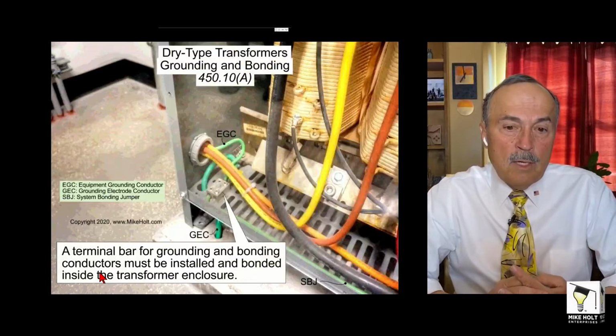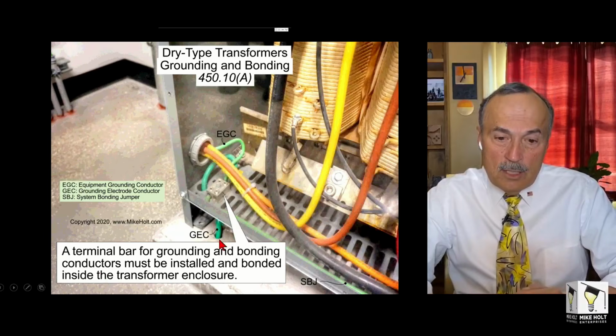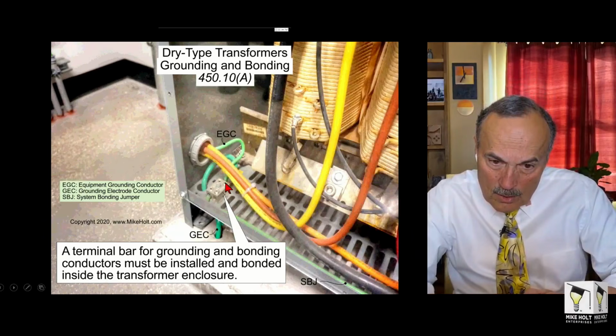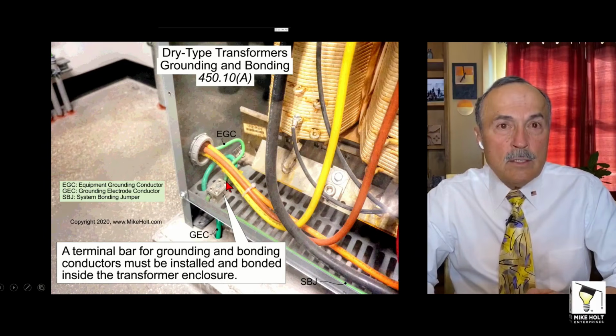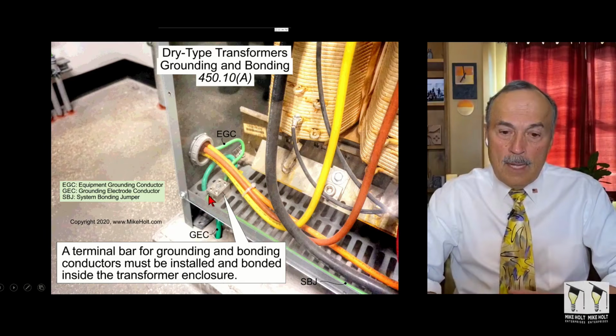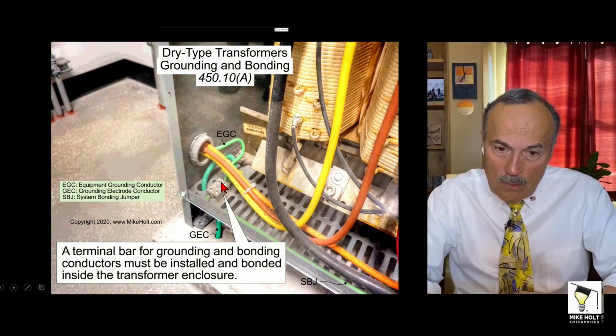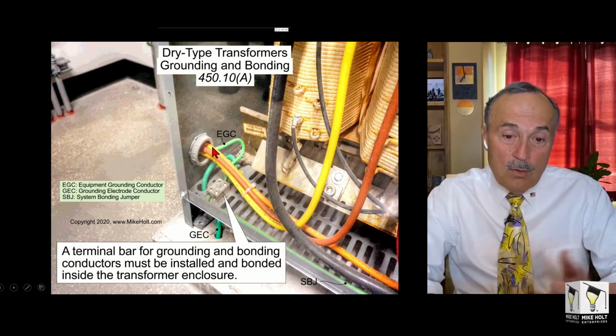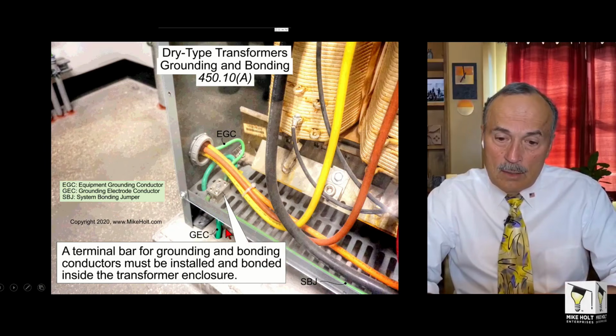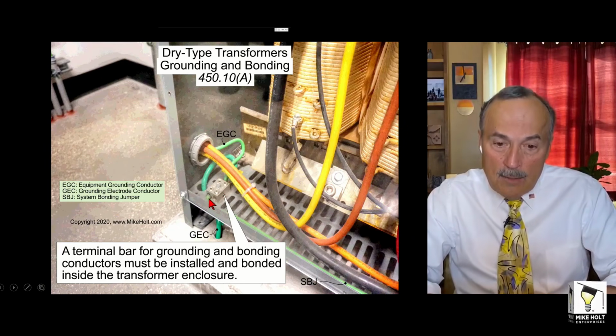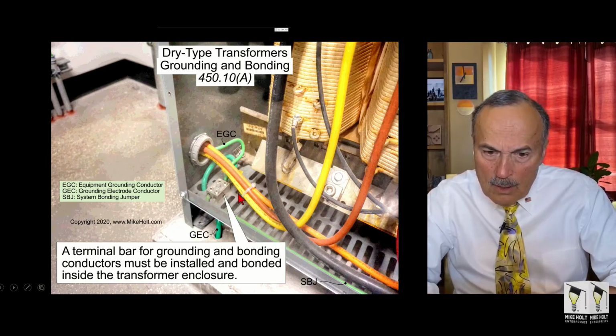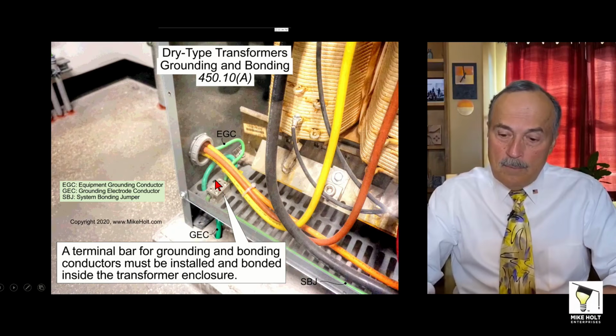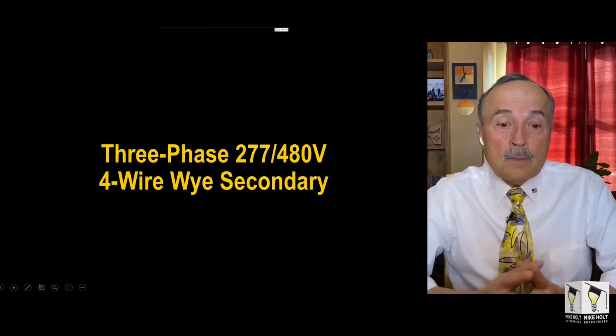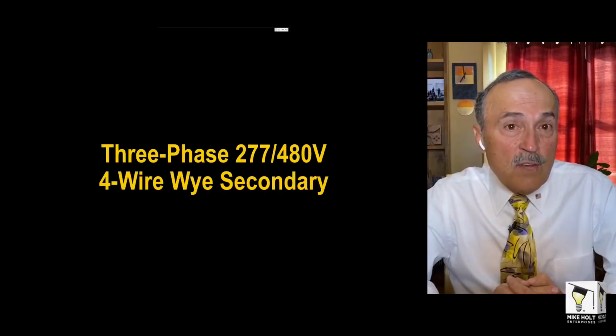And there's an example of 450.10(A). You can see this grounding electrode conductor is connected right over here to that grounding bar. And this right here is the equipment grounding conductor coming to that bar on the primary, and there's an equipment grounding conductor on the secondary. And we have a system bonding jumper not shown here. All right, 277/480 volt, 3-phase, 4-wire.